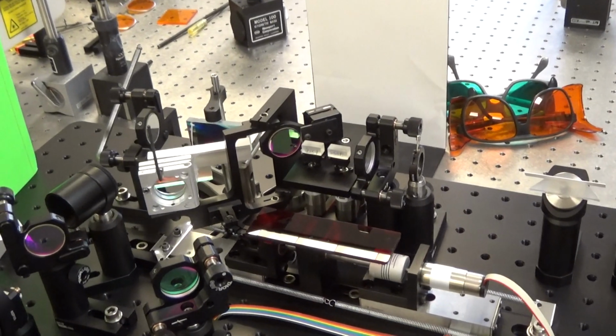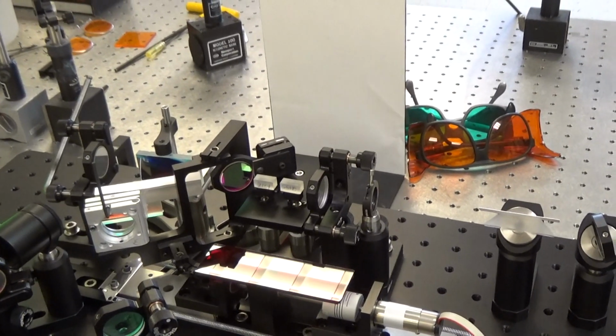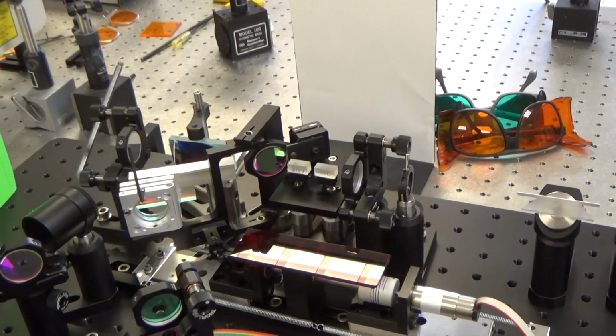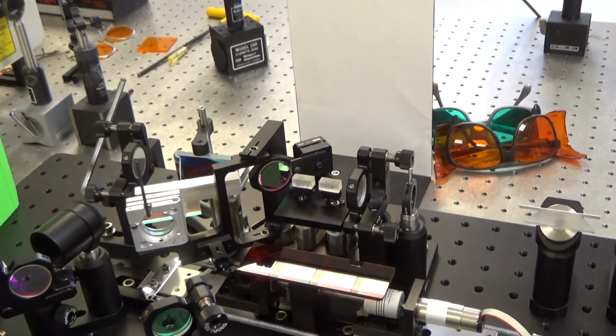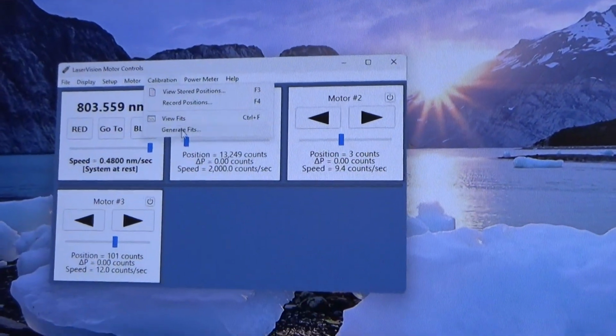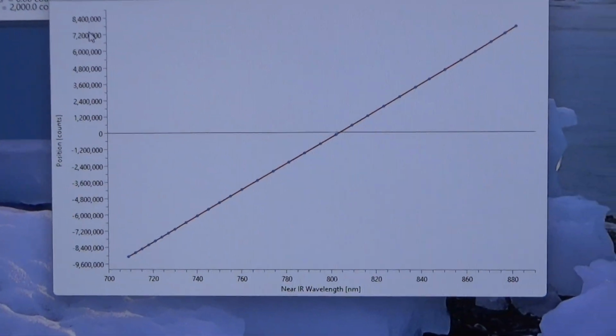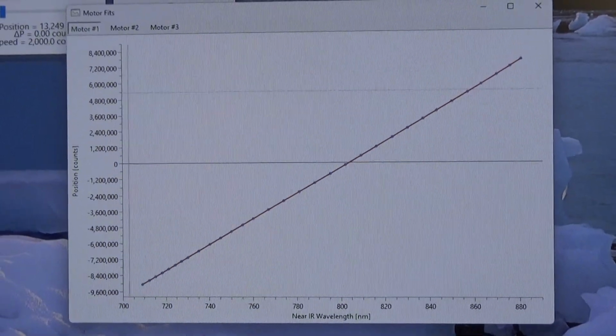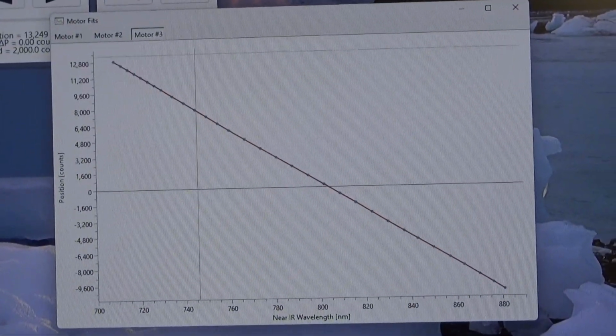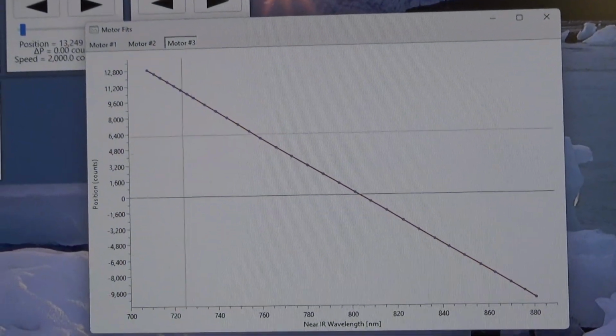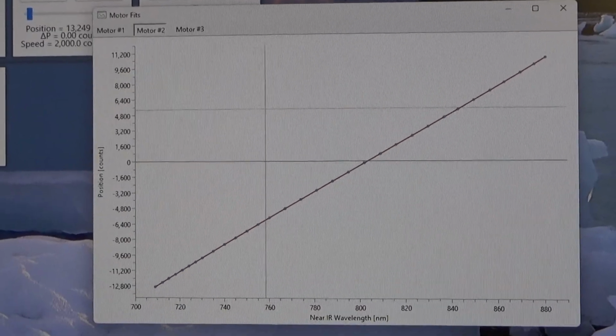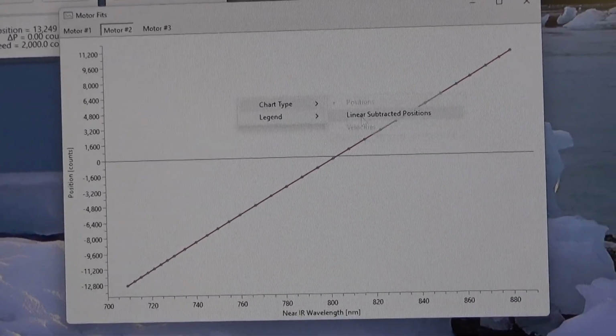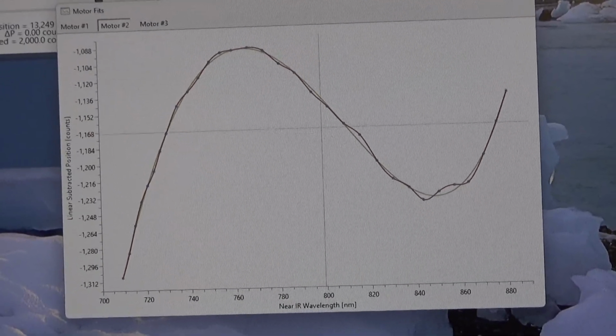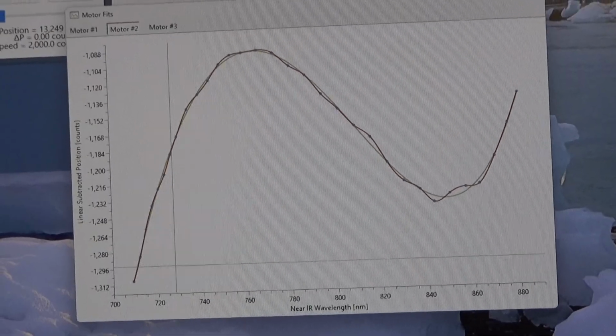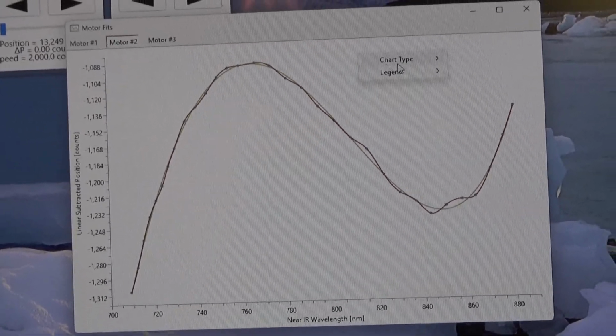The tuning behavior of the OPO stage is that each of the motors in the system has a nearly linear relationship of position versus wavelength. I can show you from the coefficients that I'm using. This is what motor 1 looks like, position as a function of near-infrared wavelength. Motor 2 and motor 3, which is turning the opposite direction, of course. Those are very nearly linear lines. But if you subtract off the linear component of that, you'll see that there is actually a little bit of deviation from linearity for these motors.